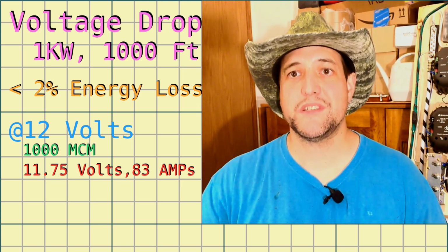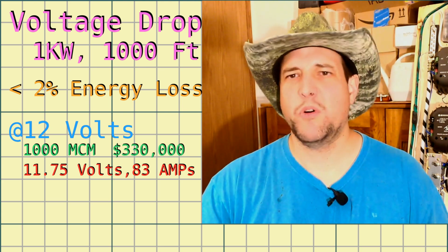7 1,000 MCM cables in parallel running 1,000 feet. And at the end, the voltage would be 11.75 volts. We got less than 2% loss of energy. That's great, right? How much did this cost us? Well, we're running 14,000 feet of copper 1,000 MCM cable, and the cost comes out to $330,000. Boy, that is one expensive air conditioner.